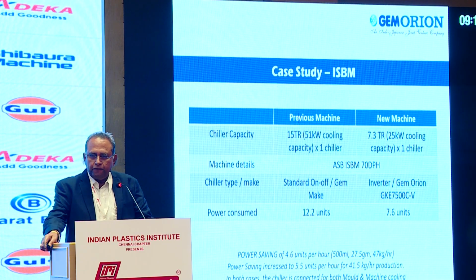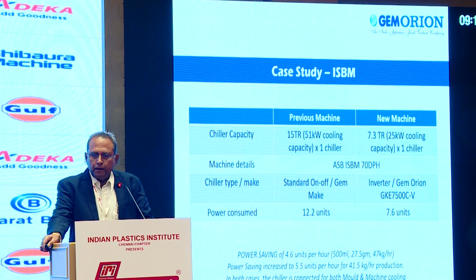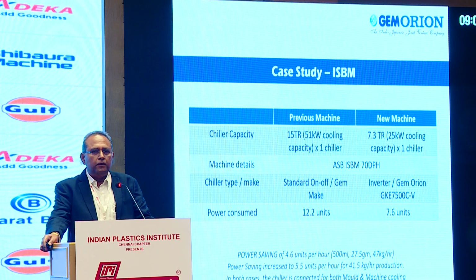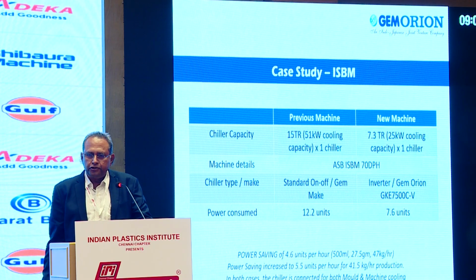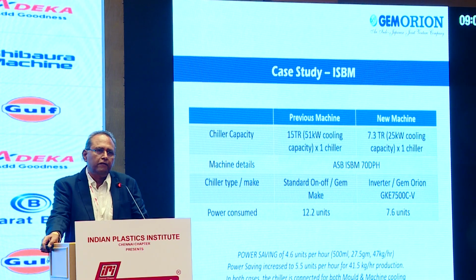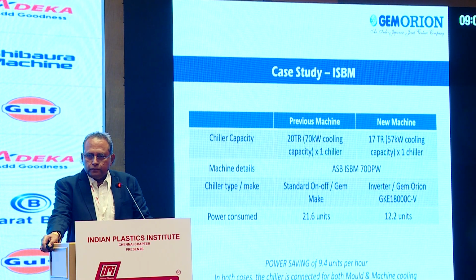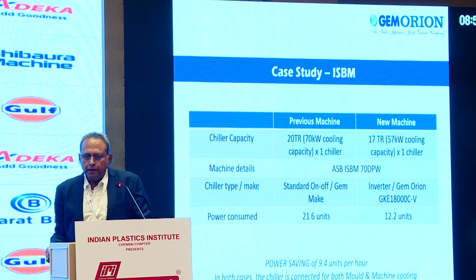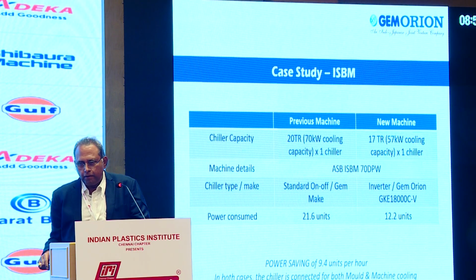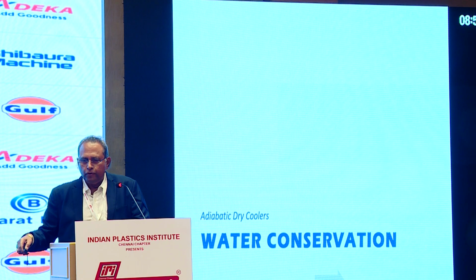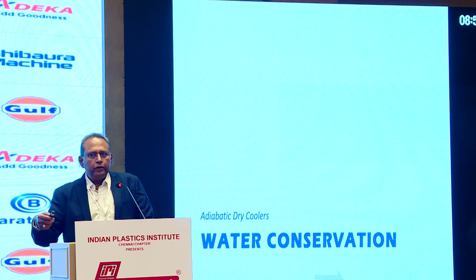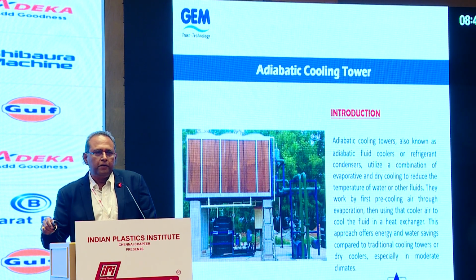So by replacing the 15 TR on-off chiller with a 7.3 TR chiller, we were able to save around 4 to 5 units. DPW and DPH machines, these two. And now moving to conservation of water with adiabatic cooling tower.